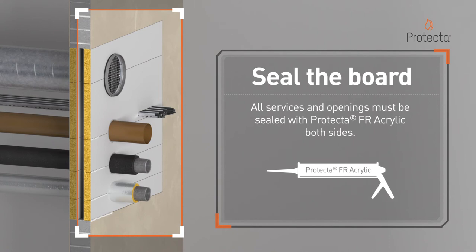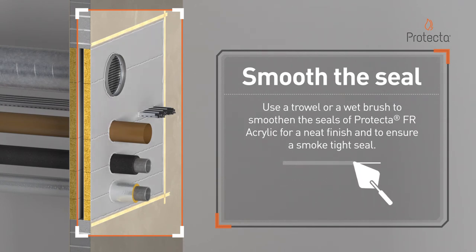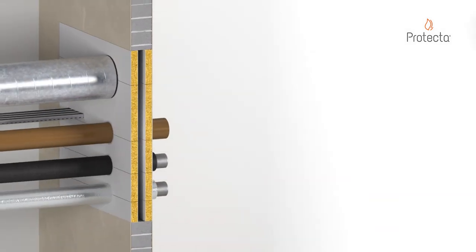All services and openings must be sealed with Protecta FR Acrylic, both sides. Use a trowel or wet brush to smoothen the seals of the Protecta FR Acrylic for a neat finish and to ensure a smoke tight seal. Repeat the process on the other side of the wall.